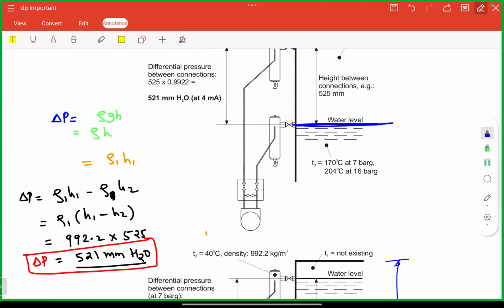When the DP transmitter will have differential pressure of 521 mm of water column, कन्वर्ट करो ना, वाटर कॉलम को आप बार में कन्वर्ट कर सकते हैं, PSI में कन्वर्ट कर सकते हैं, yes or no? Yes sir. So differential pressure of 521 mm of water column, what should be the output signal from the DP transmitter? It should be 4 milliamp, corresponding to low water level. अभी मेरे पास बॉयलर है क्या? I don't have boiler. This is all I have done, theoretical mathematical calculation.